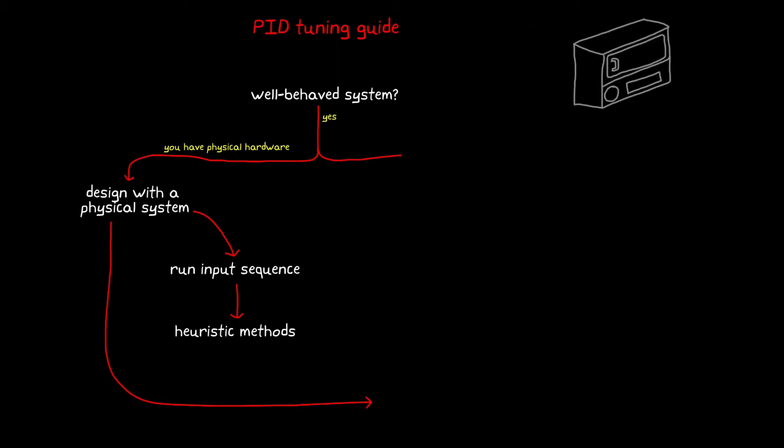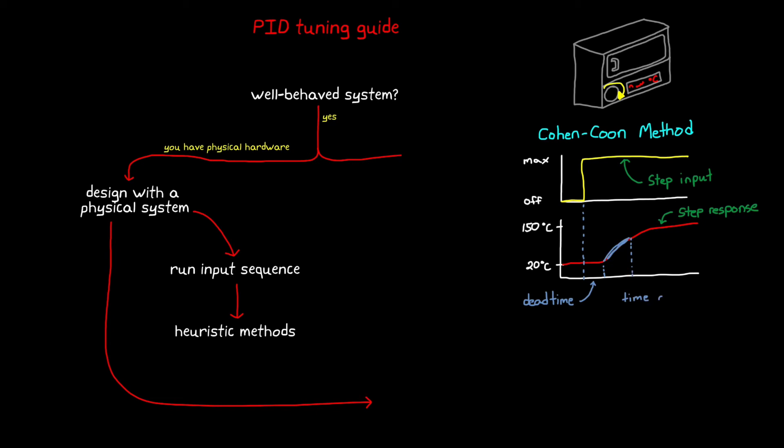For a thermal chamber example with the Cohen-Coon method, you could start with the oven at room temperature, step up the heater command to fully on, and then watch how the chamber temperature rises and eventually settles out. From this response, you could measure the delay or the dead time, the gain, and the time constant, and then plug those into an equation to get your initial gains.